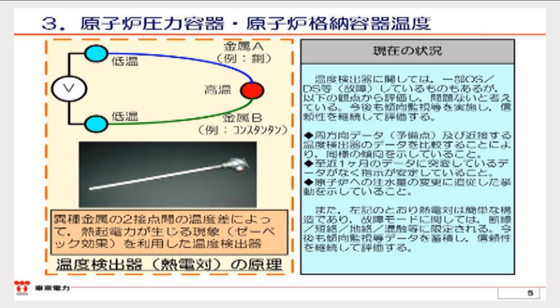Regarding the temperature detector, there were detectors such as an overscale exceeding upward and a downscale exceeding downward so far. But basically for other devices, the malfunction mode is limited to such things as disconnections, earth faults, short circuits, and mixed circuits, etc. And we think that the data collected at the moment is reliable to some extent.